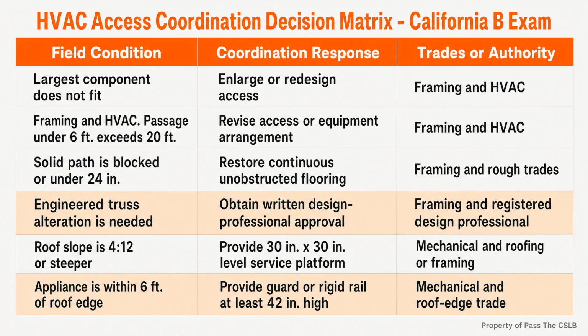Check service power. Is the required receptacle within 25 feet and on the same level? Is it supplied so that it is not on the load side of the equipment disconnect? Look at structure. Was any engineered truss member cut, drilled, notched, or spliced? If so, where is the required written approval and concurrence from the registered design professional? For roof equipment, check slope and edge distance separately. Does the roof slope trigger the level service platform? Does the appliance location near an edge trigger a guard or rigid rail?